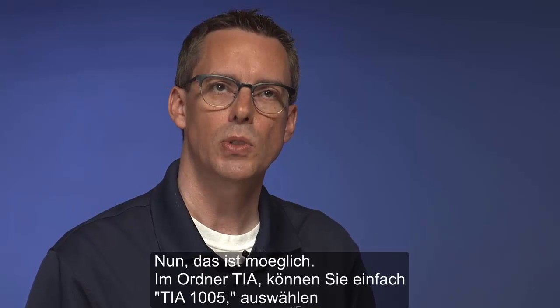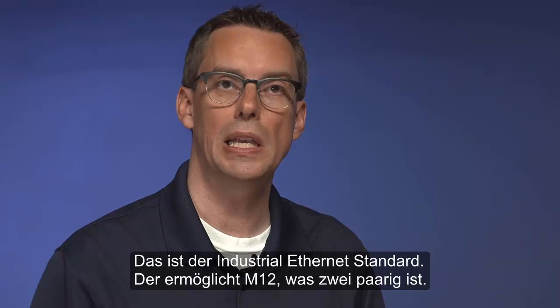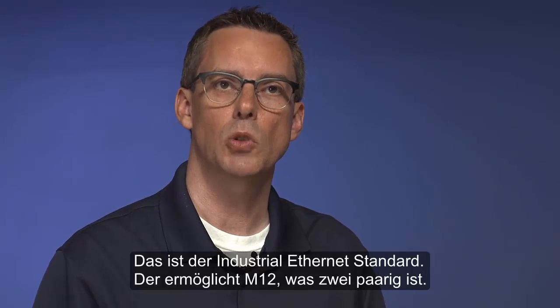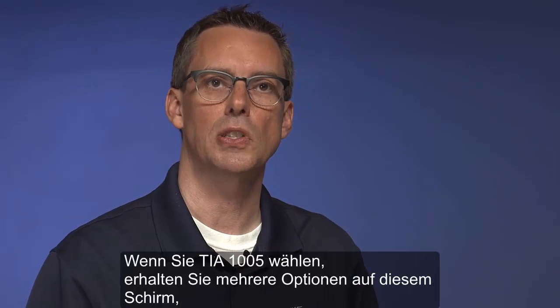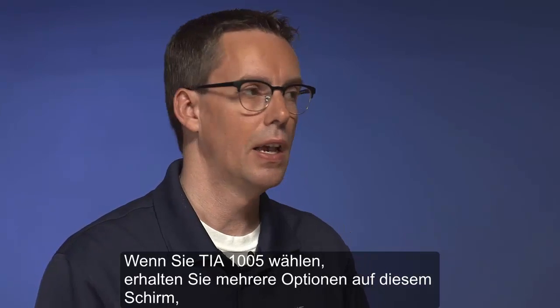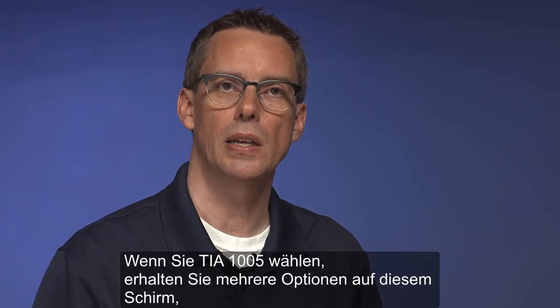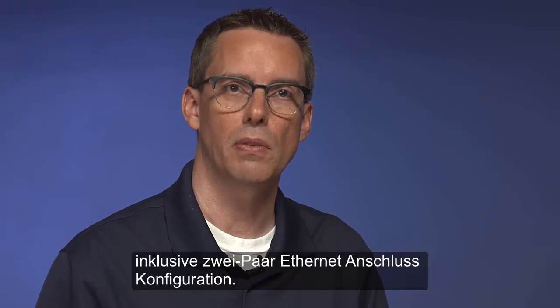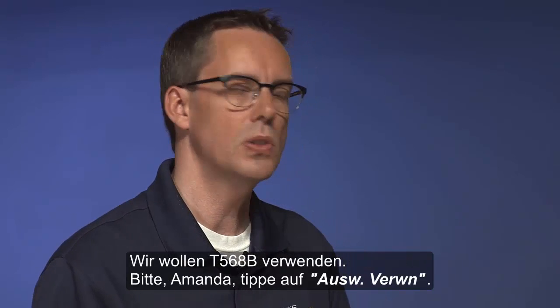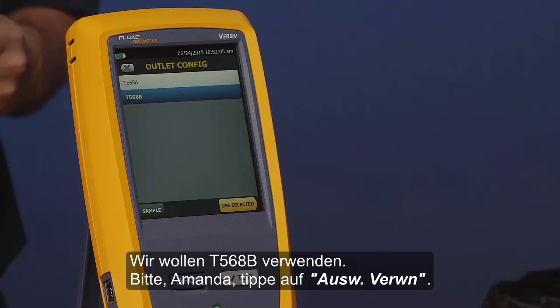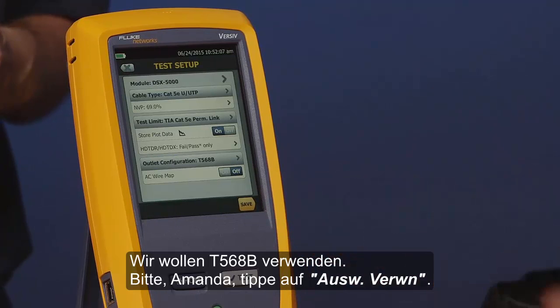In the TIA folder, you would simply select TIA 1005. That's the industrial Ethernet standard. That allows M12, which is a 2-pair. If you were to select that TIA 1005, then you get more options on the screen here, including 2-pair Ethernet outlet configurations. We're going to use our T568B, so go ahead, Amanda, and you select it.